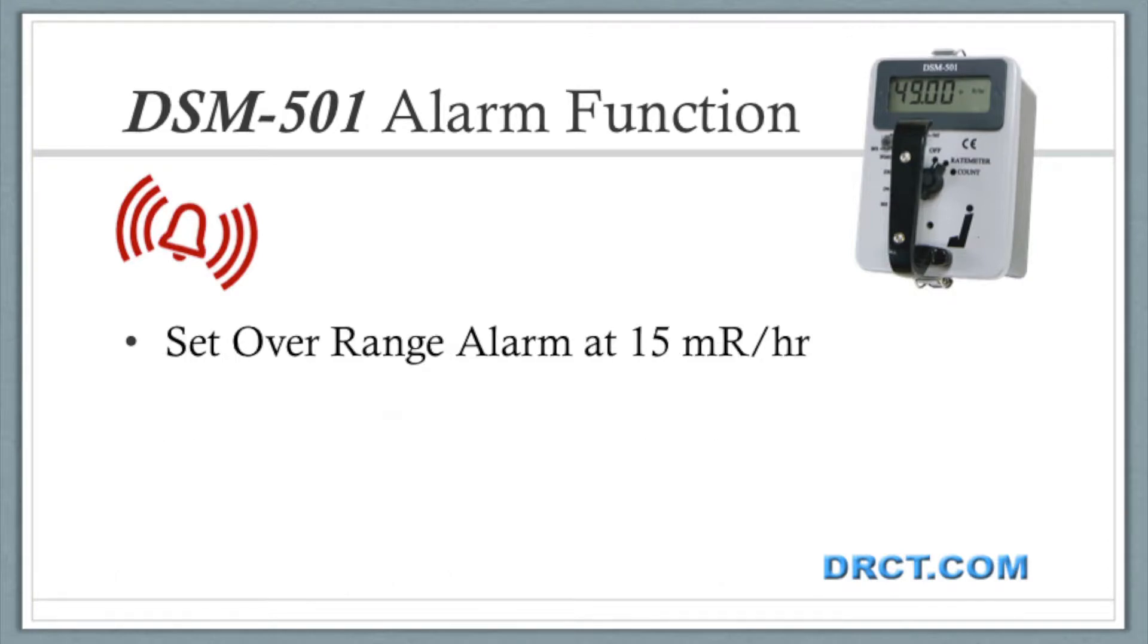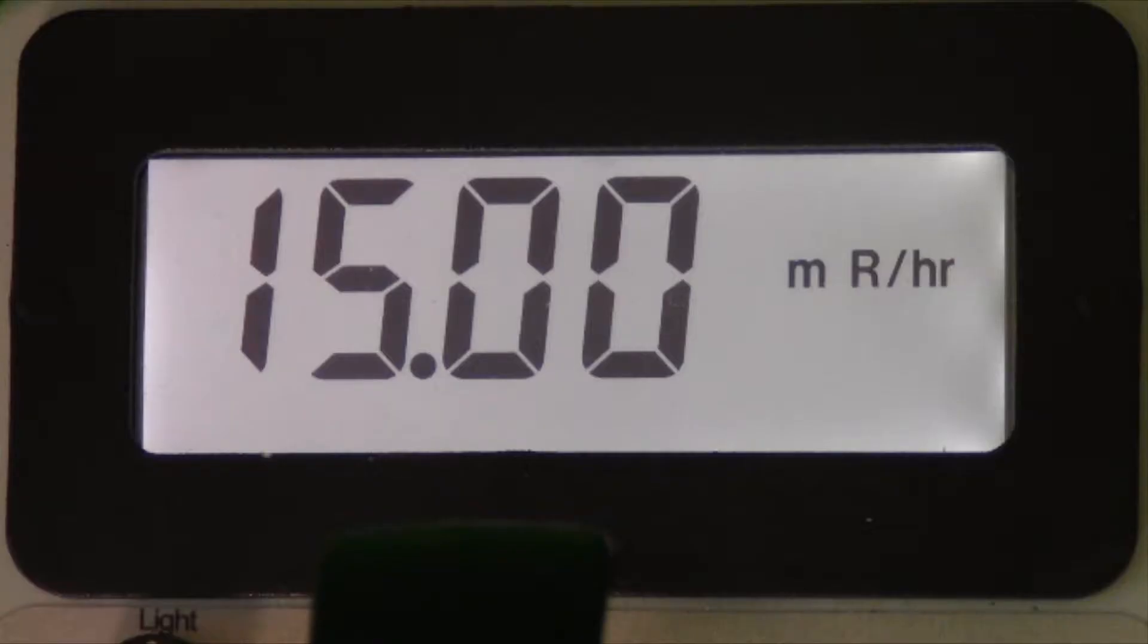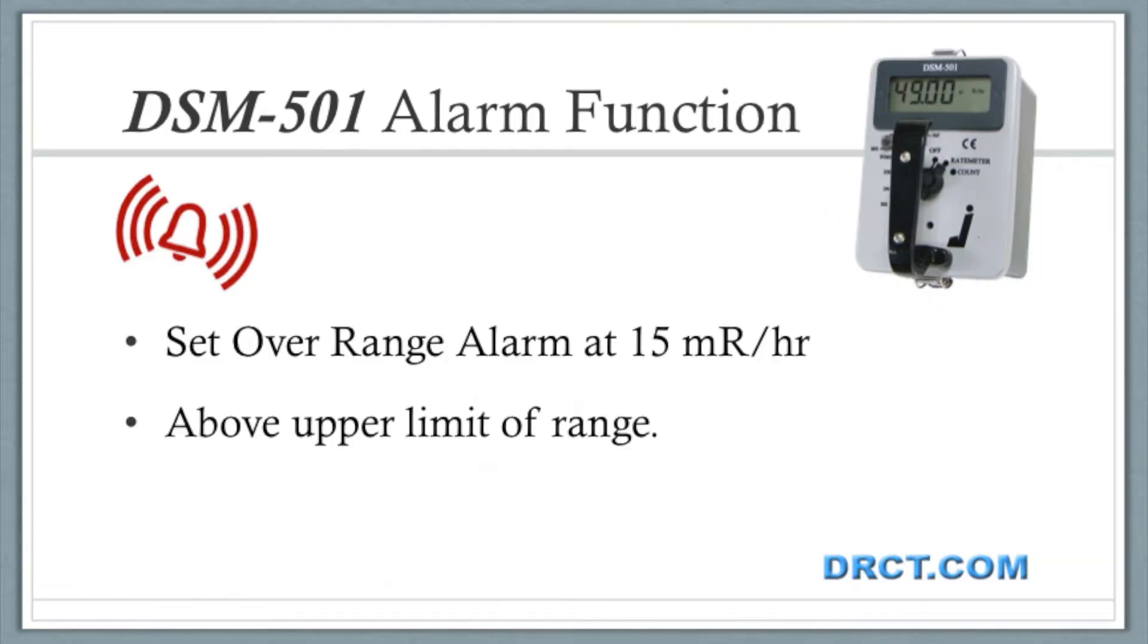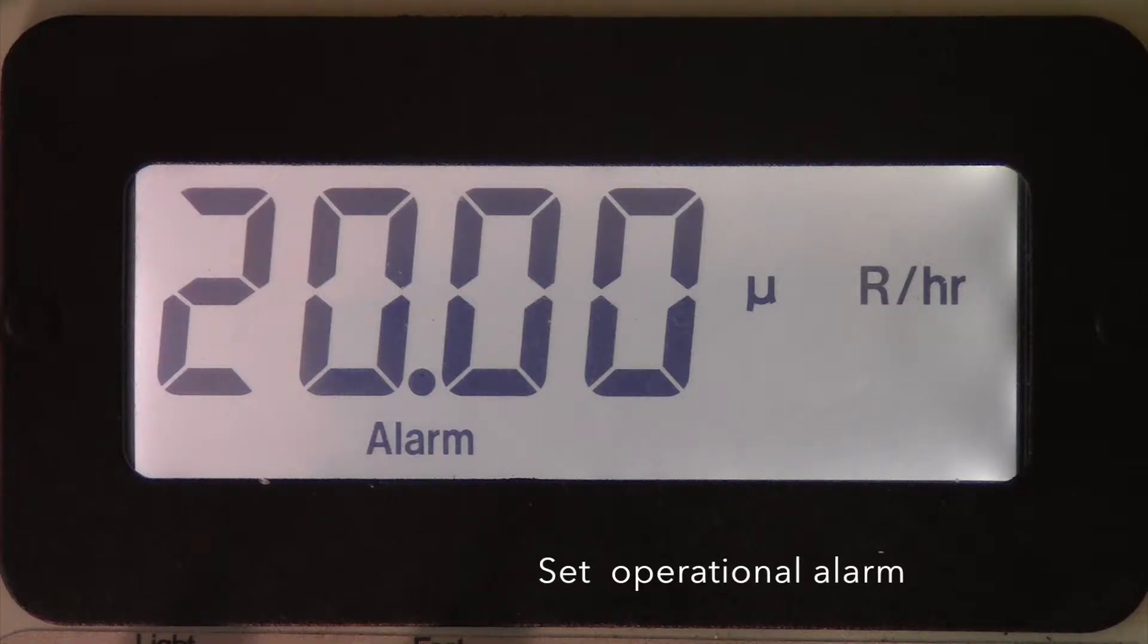The overrange alarm is often set at 15 milliroentgen per hour, somewhat above the upper limit of the meter range. Both alarms are disabled when set at zero.